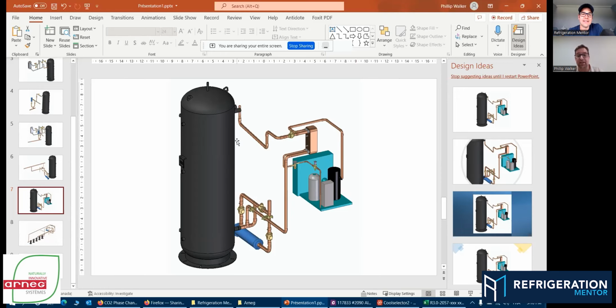Now, how do you calculate that? Pull out your iPhone when you're in the field to get some of those calculations. How do I calculate how much flash gas I truly have at this moment? It's not that difficult. I love it. I think we should do that, because I want to spend some time on it. I think that's very important, getting into the hot gas. I know a lot of people south of the border use more electric defrost and not as much hot gas defrost, but you're going to see it more and more in Canada. I worked on synthetic refrigerants, and now with CO2 it's tons of hot gas.